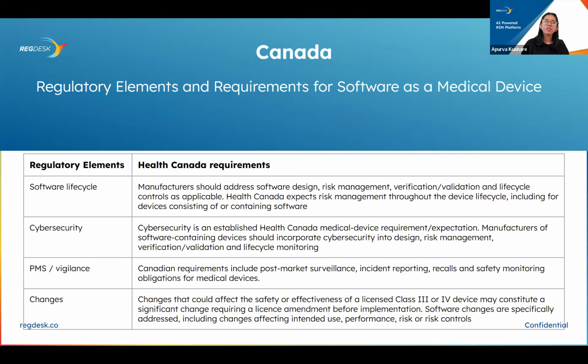Talking about changes, making changes is also an important aspect, and manufacturers should make sure that the changes they are making do not impact the safety and effectiveness of the device, and if they do, then further assessment should be done. So the changes that could affect safety and effectiveness of a licensed class 3 or 4 device may constitute a significant change. It is considered a significant change, and it can require a license amendment before implementation. And also in terms of software changes, if they are specifically addressed, including changes affecting the intended use, performance, risk, and risk control. So all of these factors should be taken into consideration when making changes to these devices.